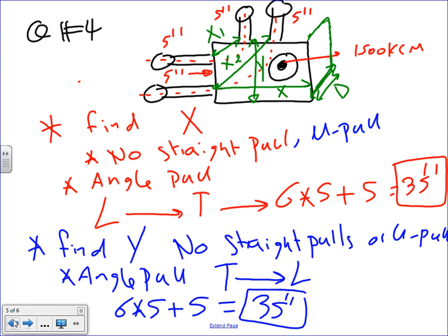Well, I guess you can by code. Then you have to say, well, I need a box that's deep enough to handle a 5-inch conduit, plus all the lock nuts and the connectors. So probably you're looking at a minimum of a 6-inch box if there's no 1500 kcm coming in the back. Why? Because you need a 6-inch and you need to be able to make a hole 1/2 inch from both sides and do the lock nuts. Anyway, code-wise, the only way you can find the depth is if you have a conductor coming from the back. So please, this baby here, very, very important. This conductor coming from the back, very important. If that doesn't exist, you can't find the box based on the code anymore. See that conductor, or conductors, coming from the back. Any questions, guys?